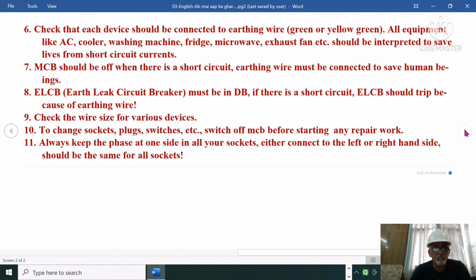So check the wire size for various devices. Wire sizes must be checked. It doesn't mean that on a thin 2.5 mm wire you put an AC. It will heat up, burn, and can cause a fire hazard. So wire size must be according to the load, as per how many amperes it is drawing. Now, to change sockets, plugs, switches, etc., switch off the MCB before starting any repair work. Always keep the phase on one side in all your sockets. Either connect to the left or right hand side. It should be the same for all sockets.